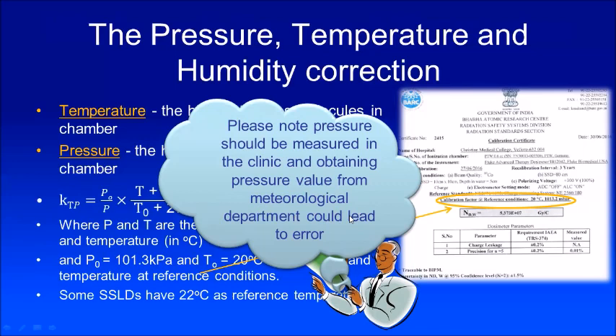Please note that pressure should be measured in the clinic — obtaining a pressure value from a meteorological department could lead to error. There is an interesting story: at one clinic located at a very high hill station, the physicist didn't have a barometer, so he called the airport to find the temperature and pressure. The airport provided sea-level pressure, but he was at a very high altitude so the actual pressure was low. As a result, his output measurement was wrong by about 15%, which resulted in wrong dose delivery to patients. Please make sure you have your own barometer and measure pressure in your clinic.